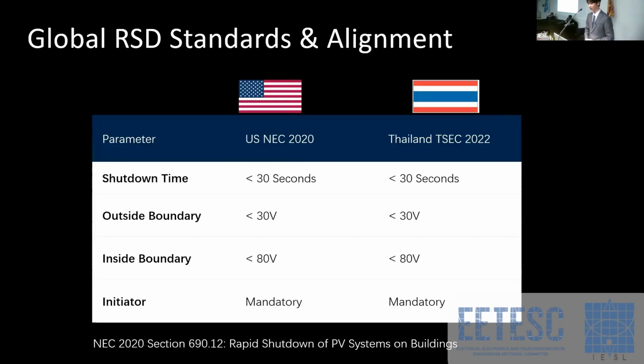It's exactly because of these risks that global regulators and international benchmarks such as America NEC 2020 and Thailand TSEC 2022 make rapid shutdown a necessity for the market entering standard. As you can see from this table, basically they are the same: reduce the source high voltage to less than 80 volts within 30 seconds. But as engineers, we know the real technical summit is maintaining zero fault operation. For some solutions, we can decrease the source high voltage to 1 volt within 20 seconds, which is much shorter than the regulation.